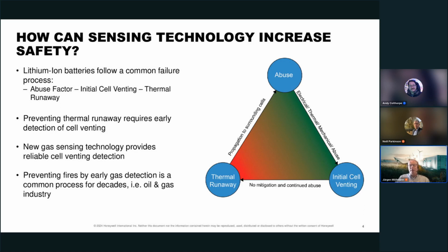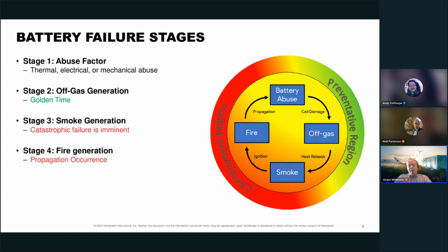To understand, this is gas detection, it's not fire detection. So we want to prevent the thermal runaway and therefore fires. This is a common process for decades in the oil and gas industry, for example, where we have high hazards as well, similar to batteries, but in a different scenario. So we should open our mind, look at what other industries can do from the technology point of view, and implement it also here on batteries. Again, in the different stages we see the battery abuse, then gas, and if we have smoke detection and smoke coming off the cell, that's most likely the thermal runaway, and then this can cause a fire.